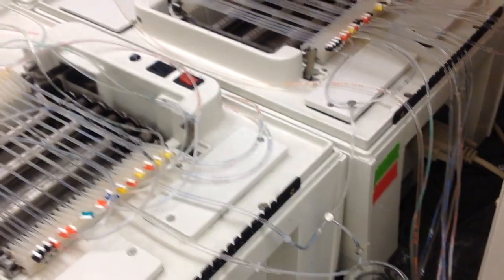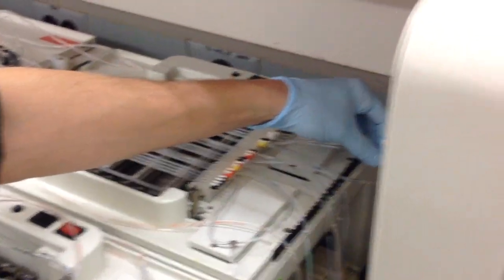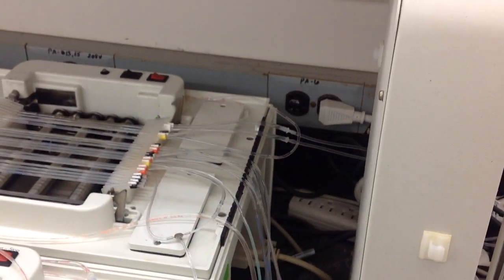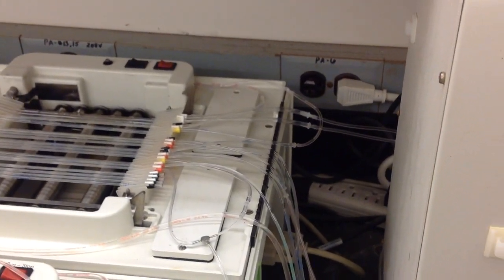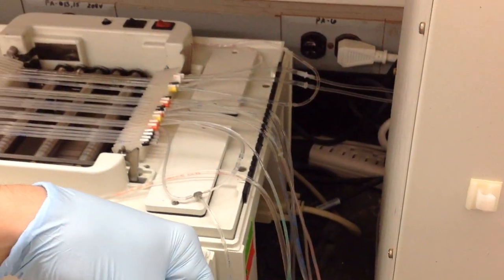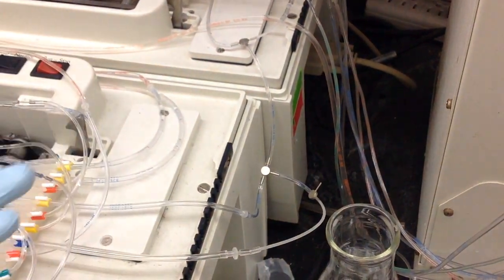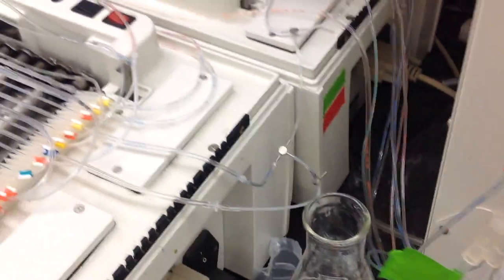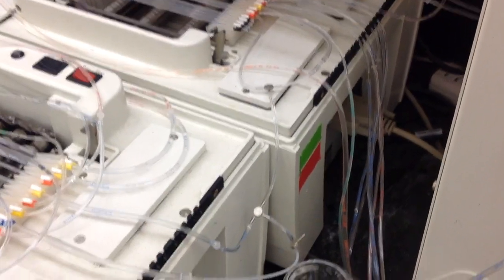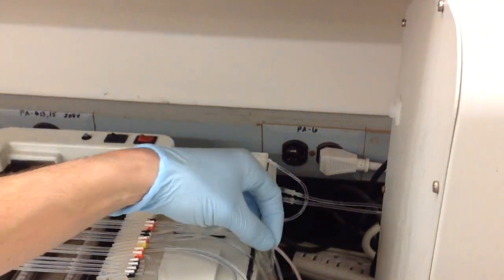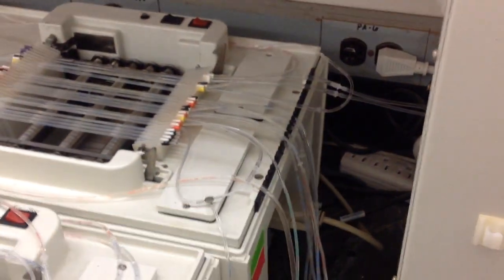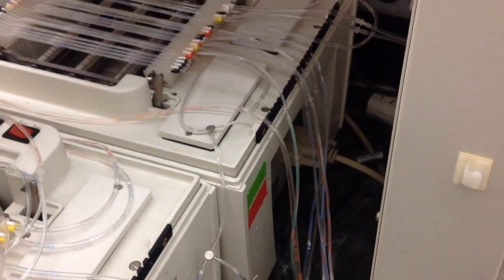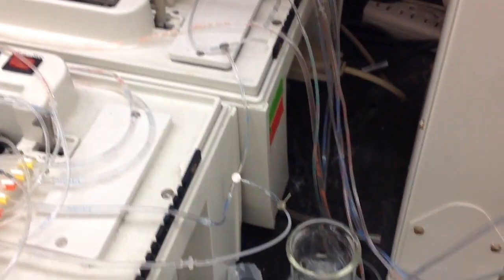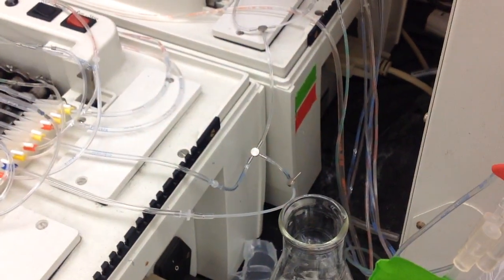So that's that. Any of the nipples, it's a judgment call. If you have them, replace them. But typically, you're not going to have enough on site to replace them all, so I typically don't, unless I feel like I really have to. If I see that as a problem, I'll replace it. But if I don't see, while the machine is running, that there's a problem, just keep the nipples and replace them as need be. Don't just strip them out. So the only thing I'm replacing is the Tygon, I guess, long story short.